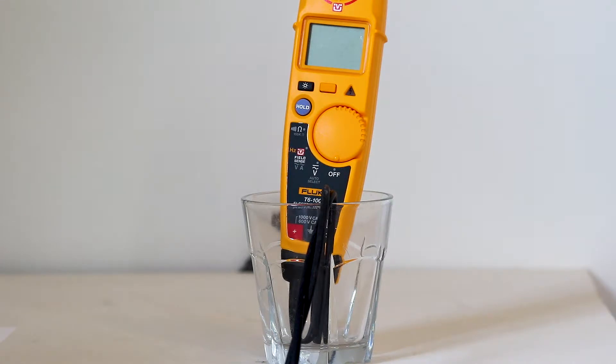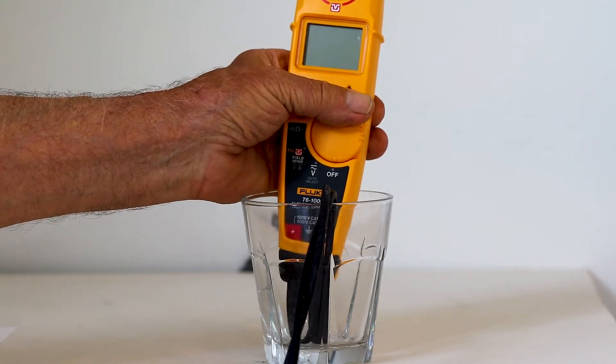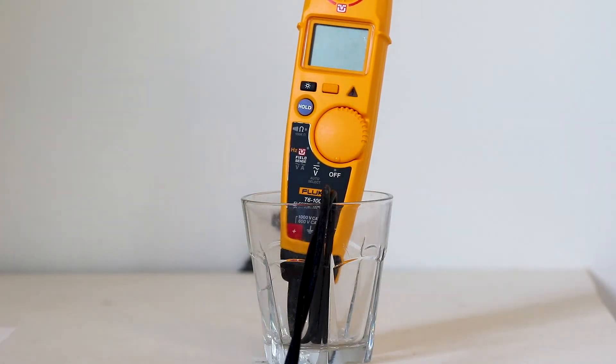Another fine Fluke instrument is the T6-1000 electrical tester. Like the 287 multimeter, it is okay for a thousand volts in a Cat 3 location and 600 volts in Cat 4 where there is greater available current. The maximum current rating is 200 amps and the tester will accommodate a four-aught conductor.